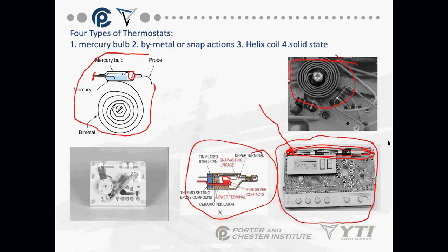So the batteries in these thermostats can make a very big difference in the operation of the system. Okay, so if you have batteries in a thermostat, and you get to a call where there's no cooling, that's why you're going to hear me say this over and over again: when you get to a service call, the first place you go is the thermostat. Not sure if that answers your question on the batteries.